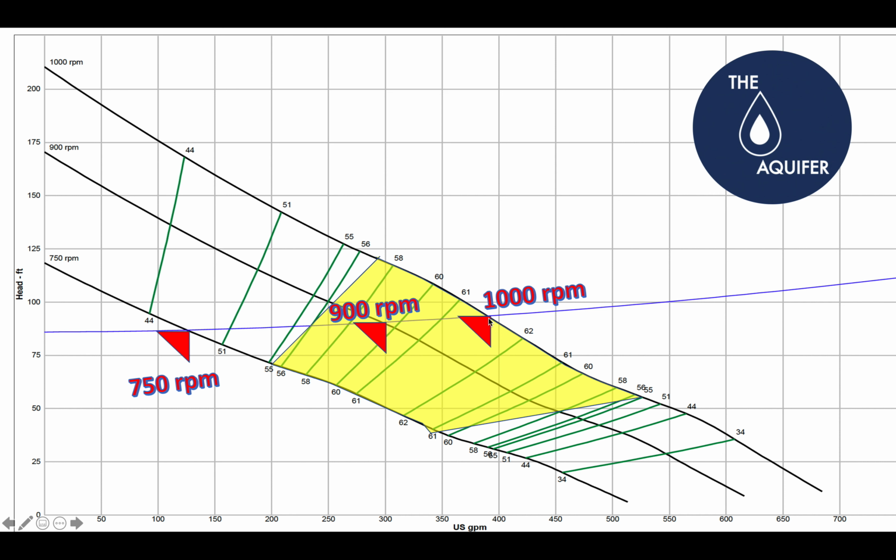So like I had shown in the pipe flow model, we're roughly 61% efficient here. This is good. We're landing in the preferred operating range, right here at a really good spot right in the middle of all that.